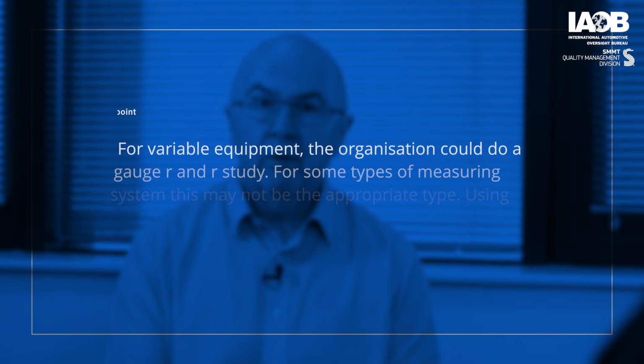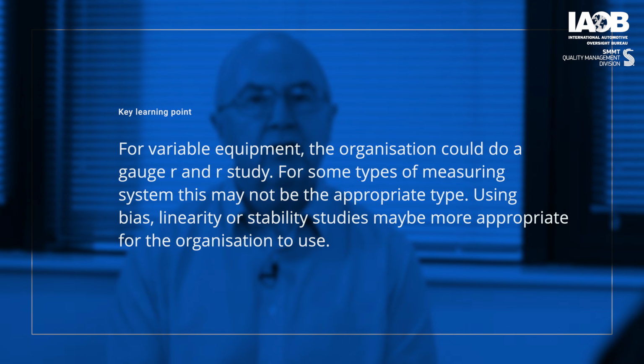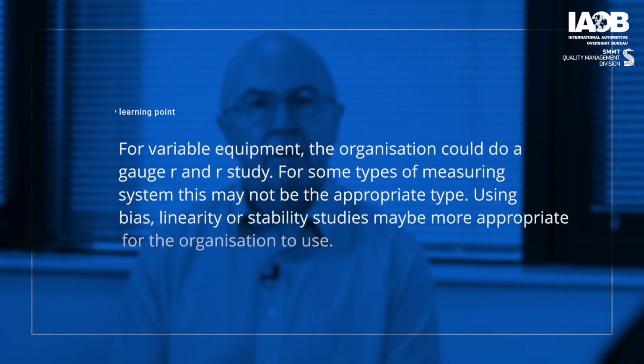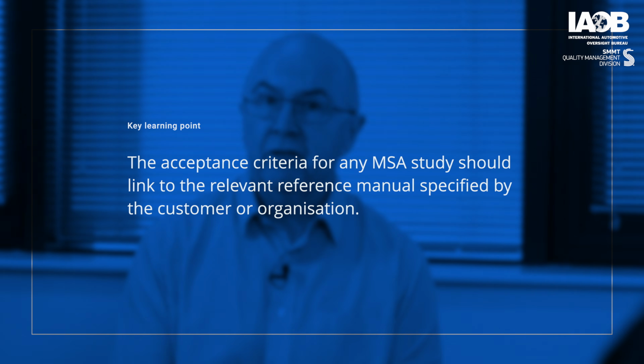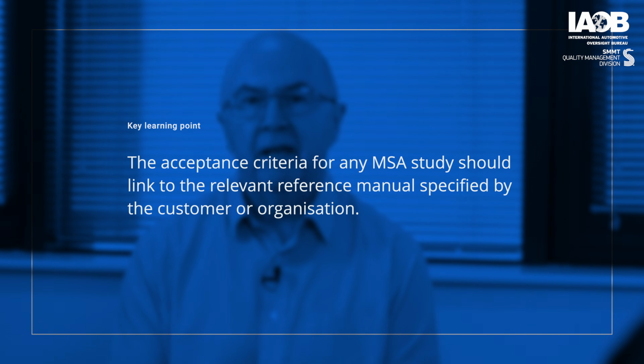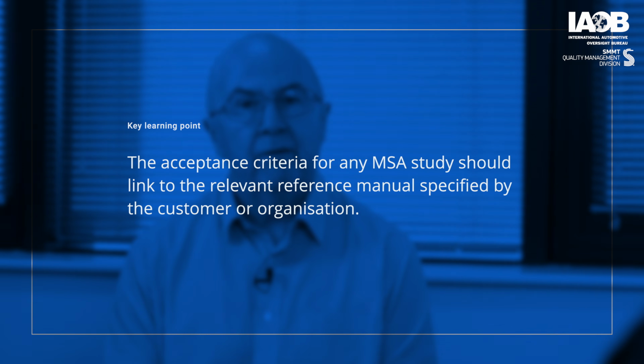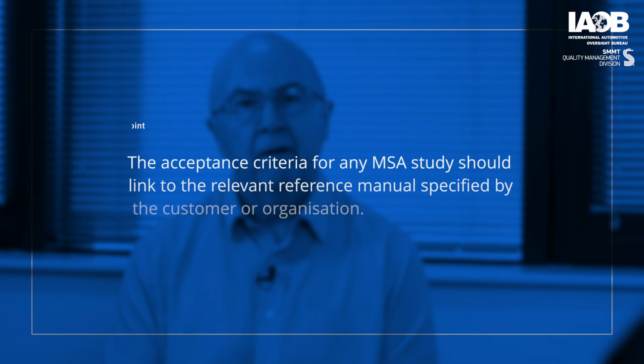For variable equipment, it could be the organization does a gauge R&R study, but for some types of measurement system, that may not be the appropriate type. So maybe the organization would use bias, linearity, or stability studies. And as Devin explained, the acceptance criteria for any MSA study should link to the relevant reference manual, either specified by the customer or specified by the organization.